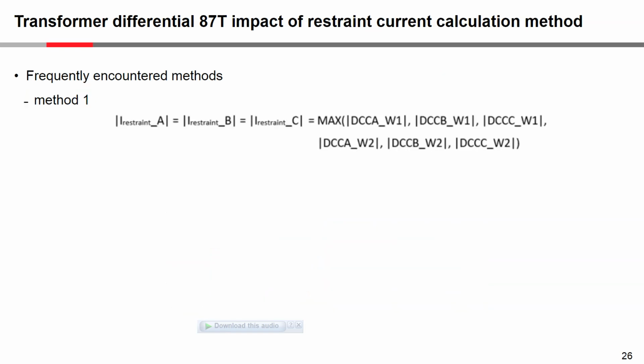Okay, so we've looked at the calculation of the differential current now, but let's look a little bit at the impact of the restraint current calculation. There are a number of methods that are frequently encountered. One of them is that the restraint current in all 3 phases will be equal. And if we look at what we call those compensated currents, and if we've got a 2-winding transformer, there will be 6 of them. And remember, the compensated current has already undergone the magnitude compensation, so they've all been brought to the same level. And so we would choose which is the biggest current of those 6, and we would apply that as the restraint current for all 3 phases.